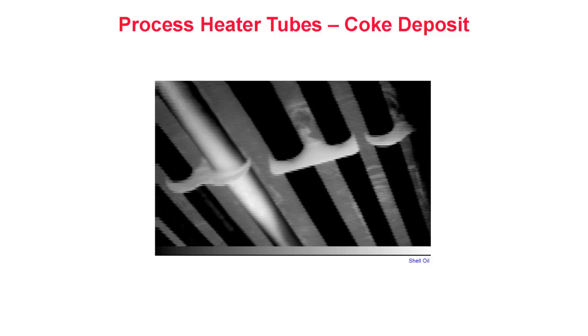Other problems such as flame impingement on tubes and air infiltration into the heater can also be detected. Properly performed, infrared inspections of heater tubes can help refiners to increase product output while maintaining safety. Performed regularly, infrared inspections can identify problems in their formative stages.